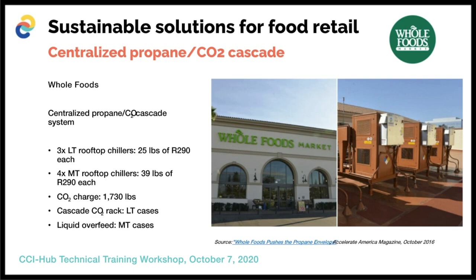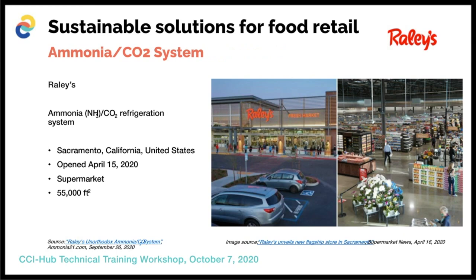CO2 charge. Moving on to one of our final slides, which is also rarely used, but in our estimate, there are about 10 stores using ammonia CO2 cascades. Ammonia is used on the high side of the refrigeration systems to cool CO2, and the efficiency results in high ambient temperatures are very impressive. Of course, the complexity and perhaps the cost of the systems are higher than standard transcritical systems. So the business case is something that has to be investigated by each retailer.